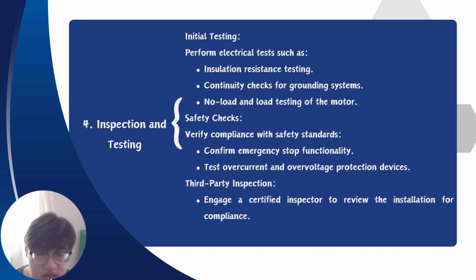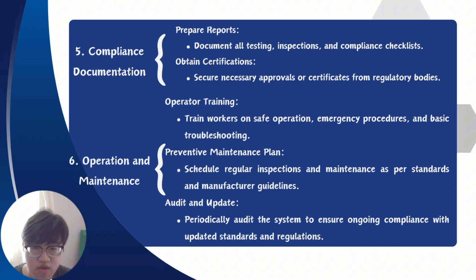Next, third-party inspection. Engage a certified inspector to review the installation for compliance. You need a third-party certified inspector to check or review that all the installation of the wiring is safe and complete. Fifth, compliance documentation. Prepare reports, document all testing, inspection and compliance checklists to make maintenance easier after that. Next, obtain certification. Seek necessary approval or certificate from regulatory bodies. The certificate can show that the wiring or installation circuit has been checked and reviewed by the certified inspector.